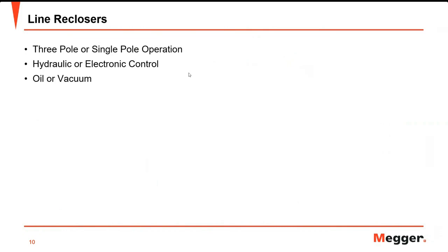Reclosers are also designed to use either oil or vacuum as the interrupting medium. In oil reclosers, the same oil is used for both arc interruption and basic insulation. Vacuum reclosers use either oil or air as the basic insulation medium.